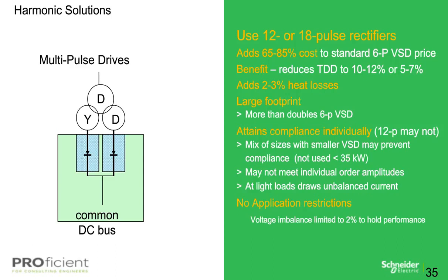Now, moving down to an 18-pulse configuration, they typically employ 3 rectifiers and a transformer with 3-phase shifted secondary windings at the 20-degree phase shift. This results in canceling 2 pairs of odd harmonic orders and leaving the 3rd unchanged. This greatly reduces the 5th and 7th harmonic order pair, as well as the 11th and 13th pair, leaving the 17th and 19th pair. When applied on a single load, about 5 to 7.5% THDI can be attained.